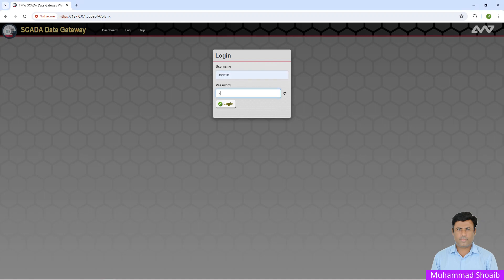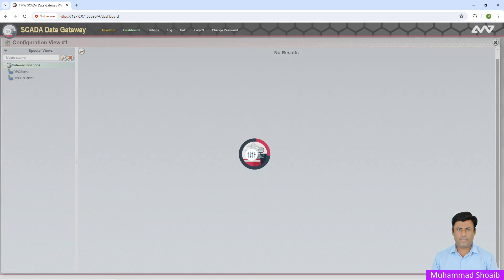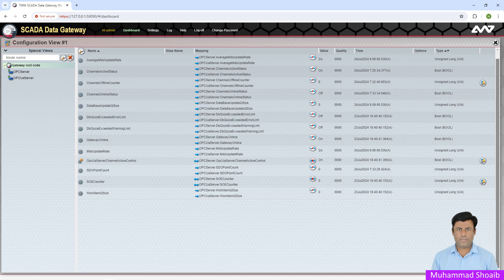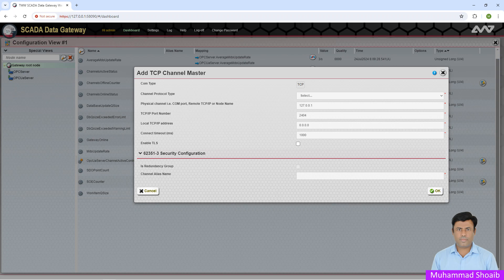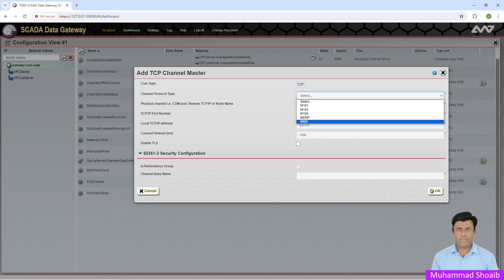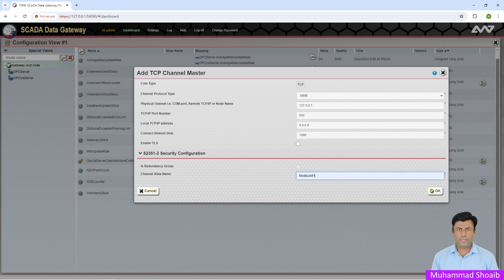Enter the username and password. Our first step is to configure the Modbus protocol in SCADA Data Gateway. We'll configure the SCADA gateway as a Modbus TCP master. Right-click and click on TCP Channel Master, then select the protocol — for our case, Modbus Master.